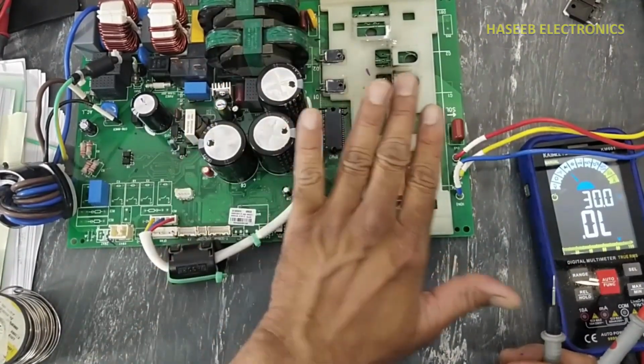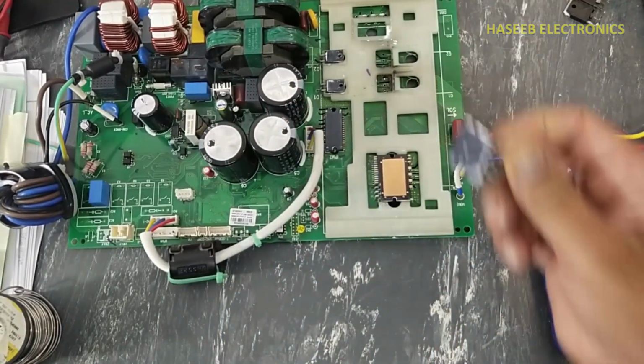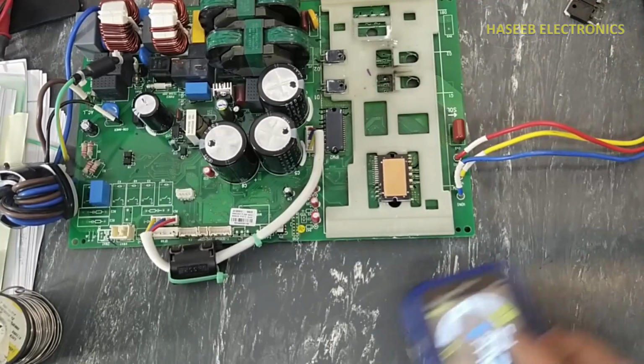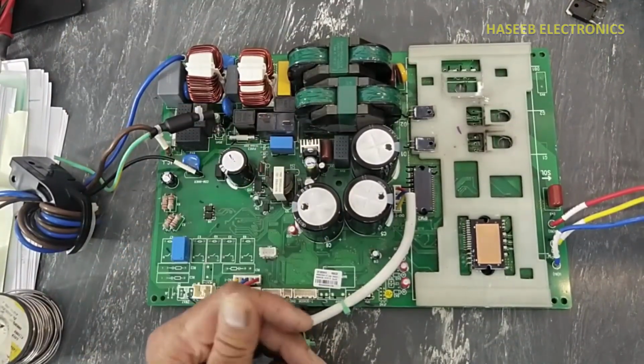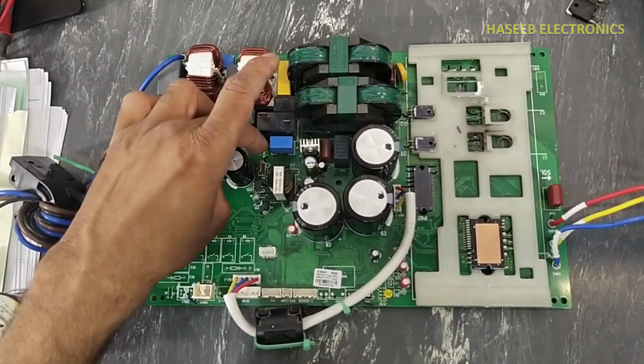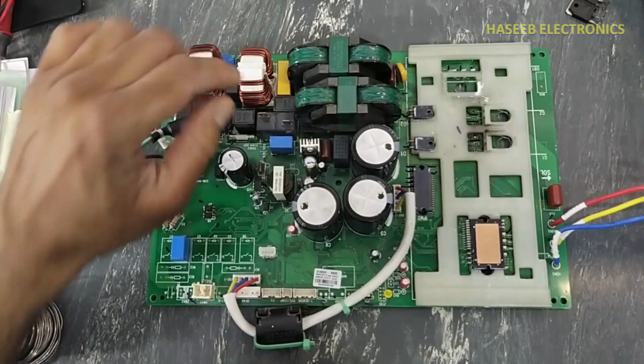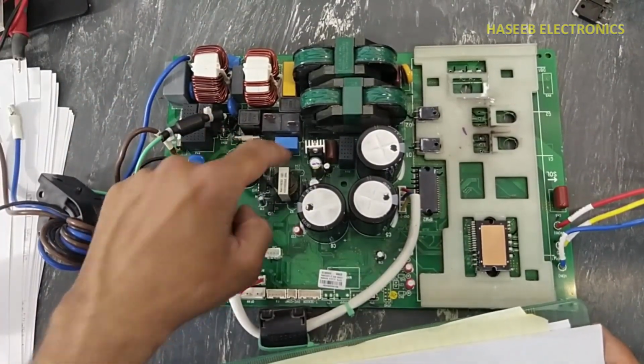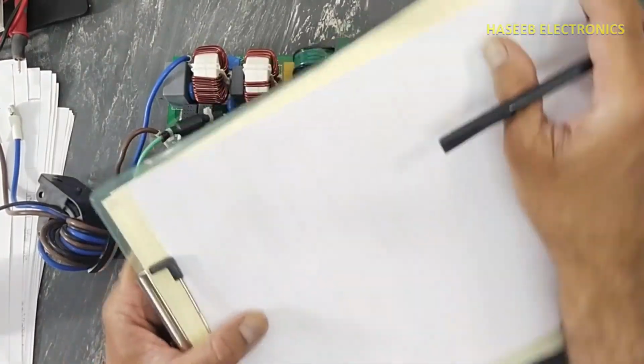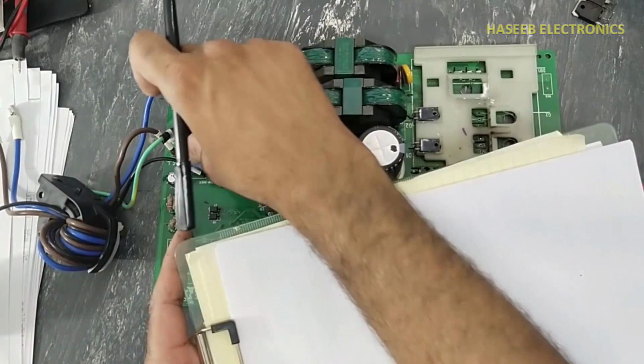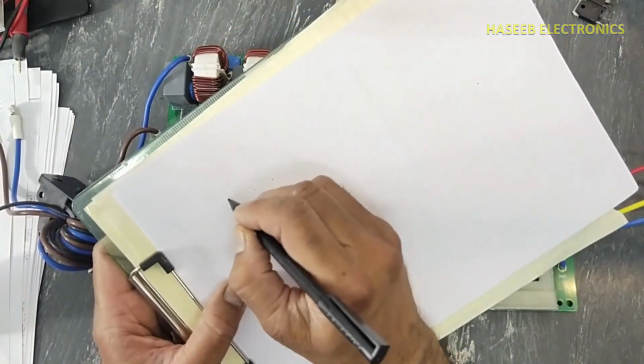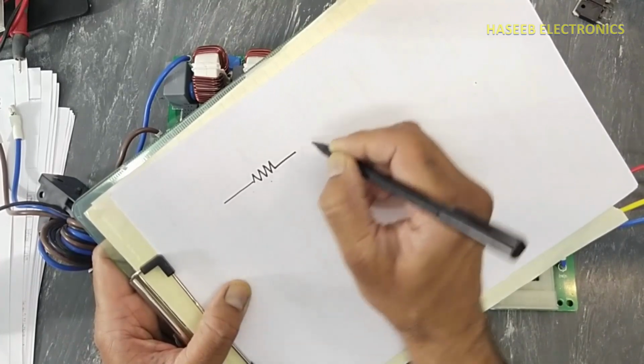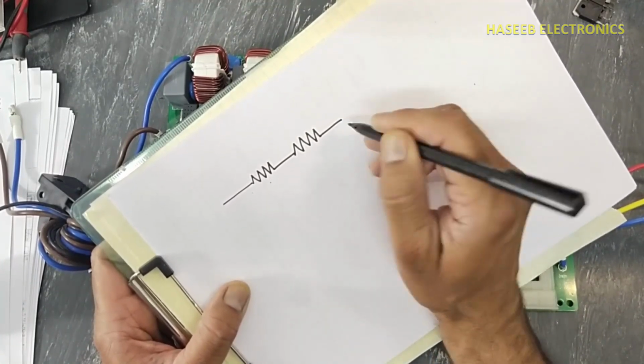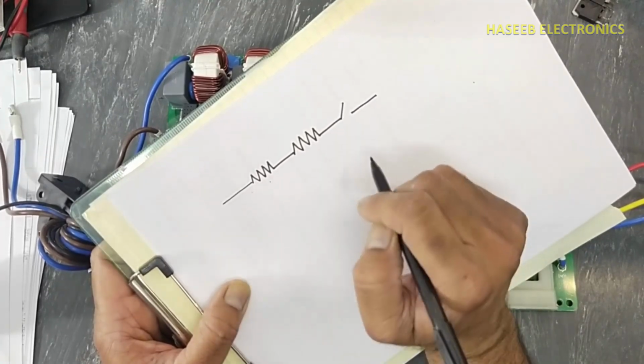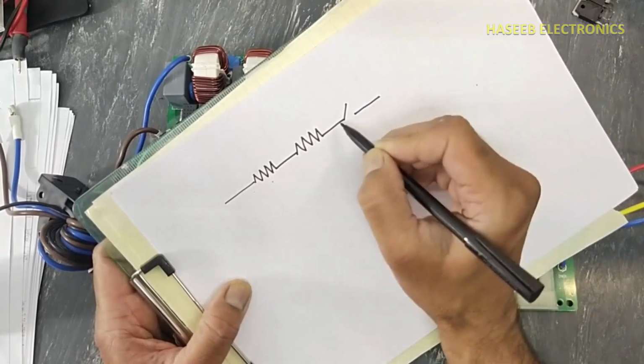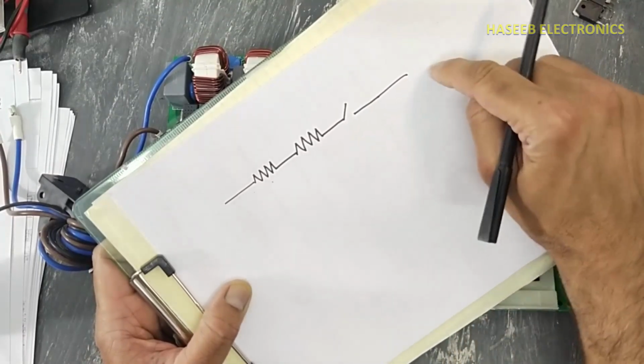So we will turn on this board without these IGBTs and without this bridge rectifier. So we need to verify this section. The second thing, to turn on this board, we need to jumper the J2, J3 connector. Why do we need to make a jumper? Because this circuit supply, after this protection circuit, EMI filter, will reach the PTC. First PTC, second PTC, and then it has a turn on relay, power on relay. Then the voltage will go out to the bridge rectifier.